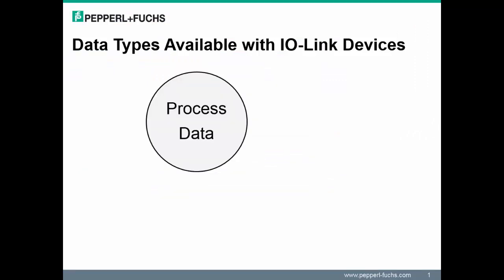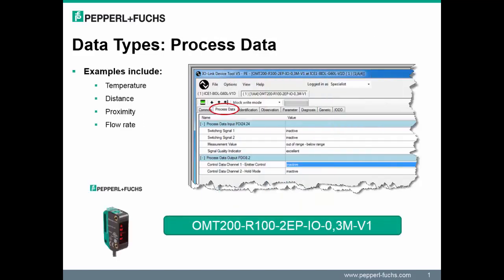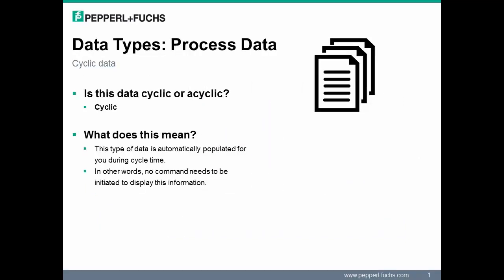There are three types of data available with IO-Link devices: process data, service data, and event data. Process data is information such as switch signals or distance values. On this slide, we take a closer look at the process data of an R100 sensor connected to port 1. Process data is cyclic data, meaning the data is automatically populated on a cycle time. In other words, no external commands are needed to initiate displaying this information.